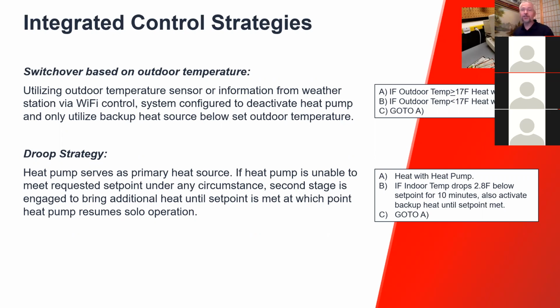You know, maybe 17 degrees isn't the right level. Or what if it's a really sunny day? It might be 17 degrees out, but it's really sunny. And so the windows on the south side are going to generate heat, and you don't really need to have the backup heating system switch over entirely. I mean, there's a lot of environmental variables around selecting that temperature, and you don't really know whether it's going to be needed or not.